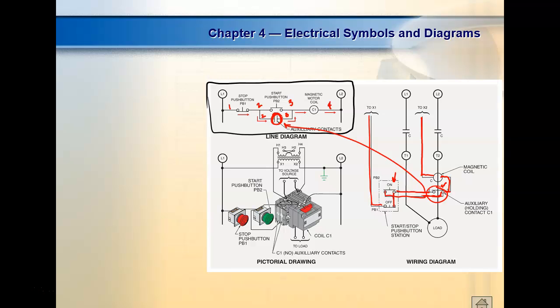So we'll look later at how we number wires and how we number rungs. On a ladder diagram you know exactly where the relay contacts are, because they're drawn in rungs, and they consist of lines. So this right here would have 2 lines—this would be line 1, and that right there would be line 2. In motor controls, we number lines, we don't number rungs. This gets people in PLCs confused, because in PLCs they number rungs instead. And Siemens doesn't call them rungs—Siemens calls them networks.